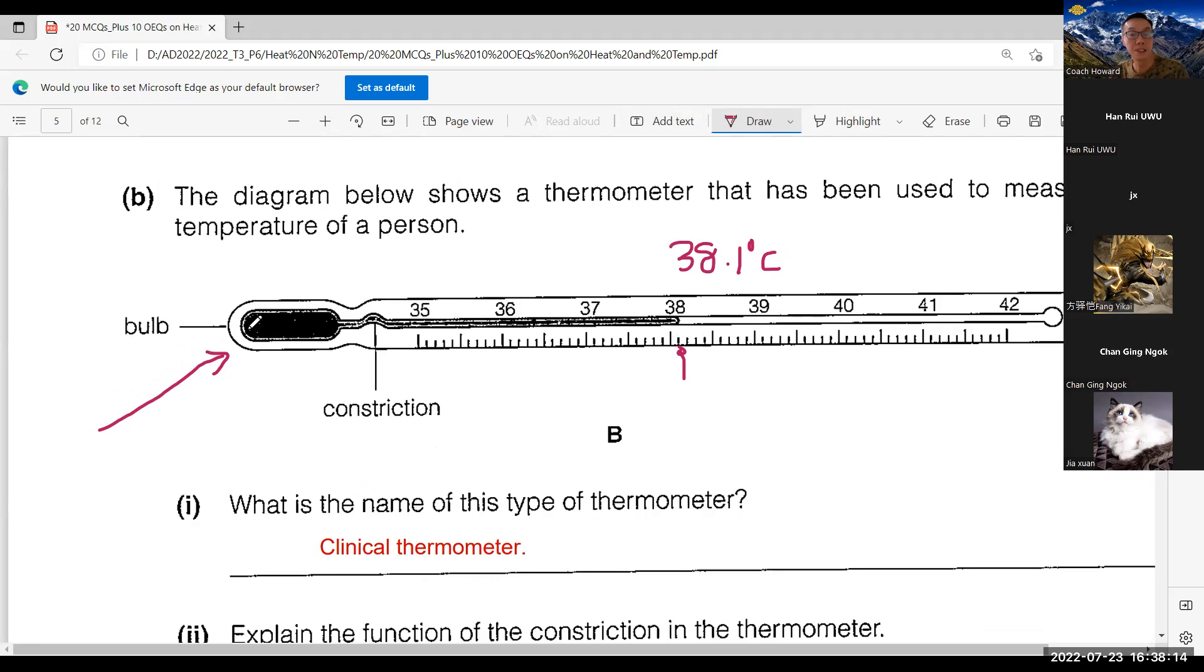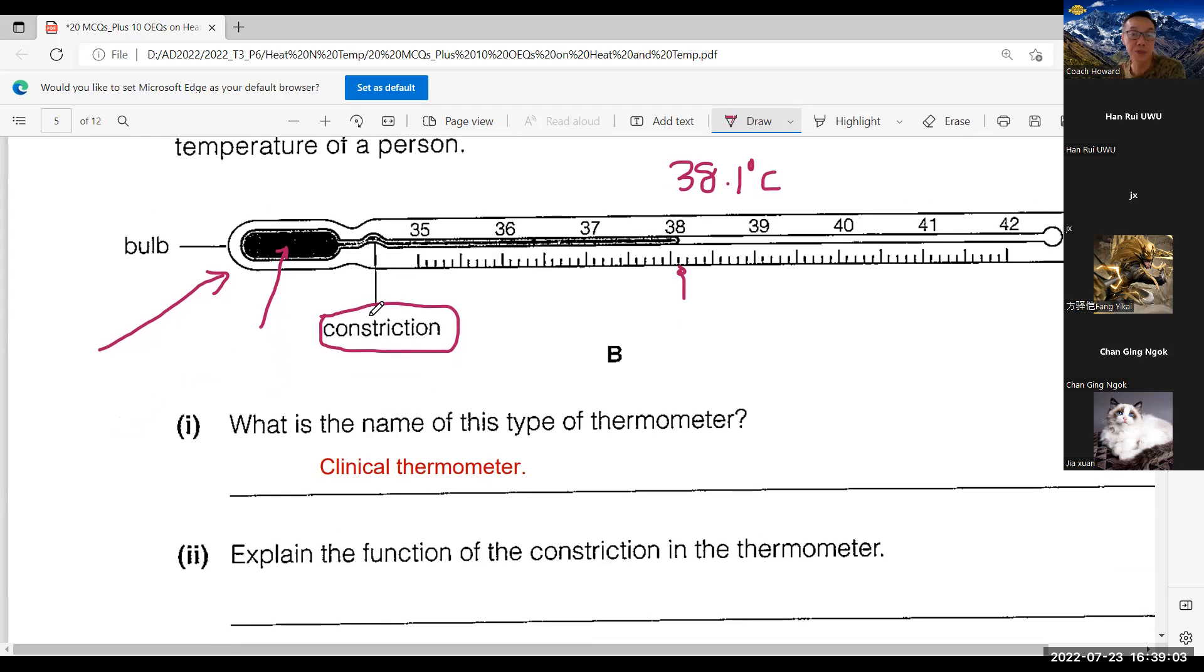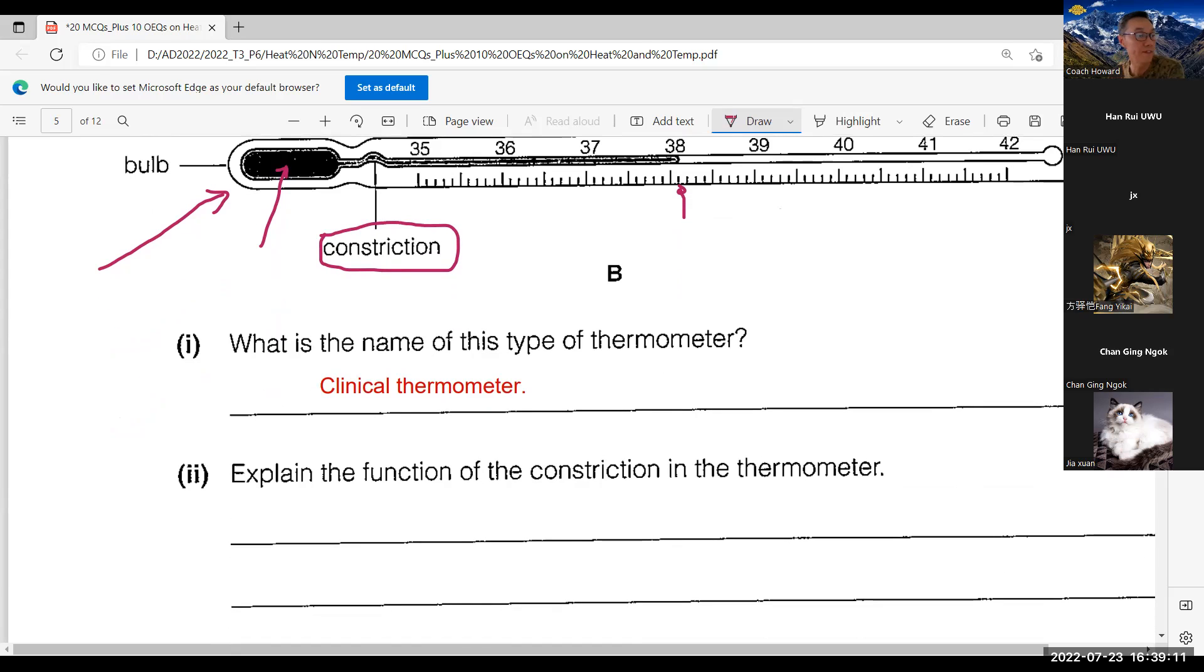When you put under your tongue for about one minute, the bulb actually will gain heat, causing this liquid inside, which is mercury, to expand. As it expands, it's forcing itself to a narrow tube, the capillary tube. It will stop at a point where it reaches the maximum temperature. Without this constriction, when you remove the thermometer from the patient's mouth, the temperature will drop immediately.